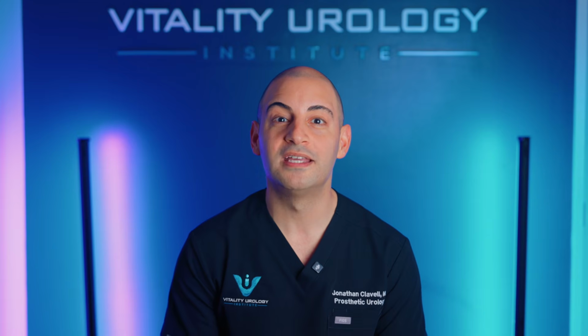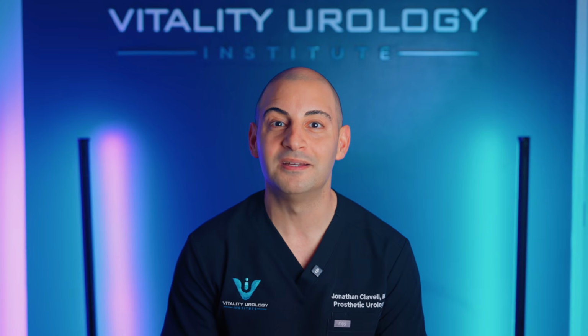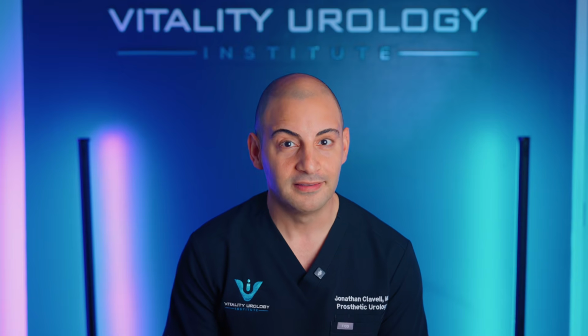One very cool feature that the deflation mechanism of the MS pump has is that when you press the deflate button, the pump vibrates, and this way gives the user feedback of when the implant is deflating. Why is this important? Because sometimes, and specifically when you first start cycling the implant, many patients do not know if they are pressing the deflate valve correctly. And when they feel that vibration within the pump, they get that eureka moment and get excited because now they know that they are deflating their implant. This is a feature that only the MS pump has.